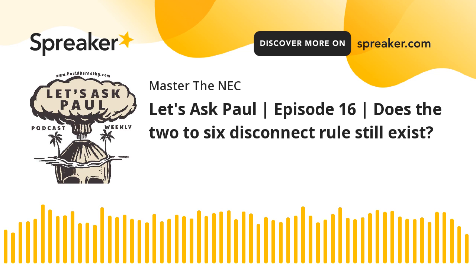That's the general rules, and of course, if you only had the one, then you didn't need to go to 230.72, which is the grouping of disconnects, because you obviously only have one. So we're very much talking about the 6 disconnect rule here, so the up to 6. Now, here's what it says. I'm going to read it to you in 230.71.